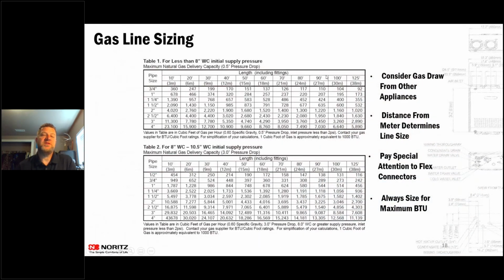So gas requirements. I'm sure everybody's been through RMGA trainings. Everyone knows how to size gas lines. With Utah, you do have to derate for the elevation. So same principles apply when sizing tankless water heaters. You can't just replace a 40-gallon water heater and throw a 199,000 BTU tankless water heater on the wall and expect it to work just fine.